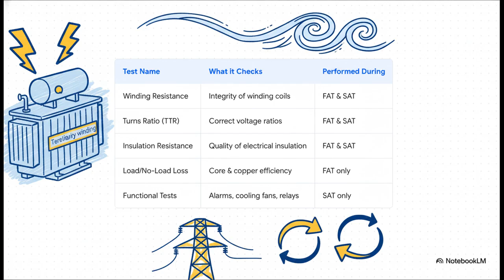And the level of detail in these tests is just incredible. During both FAT and SAT, they're checking things like winding resistance to make sure all the copper coils are perfectly intact. They run a turns ratio test to confirm it's going to produce the exact right voltages. These checks guarantee that every single part, including our hero, the tertiary winding, is working exactly as it was designed to.